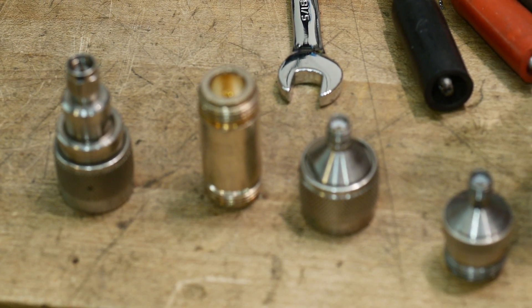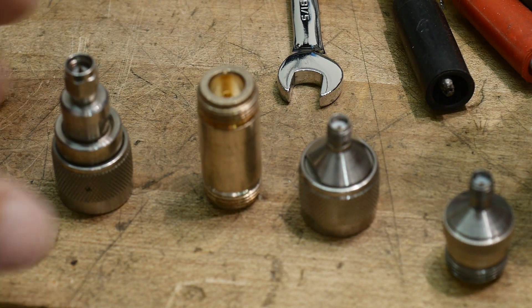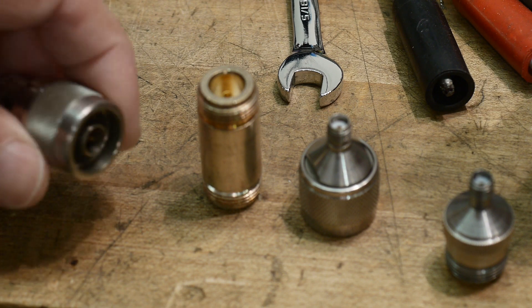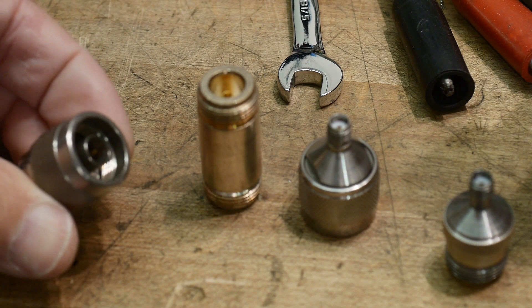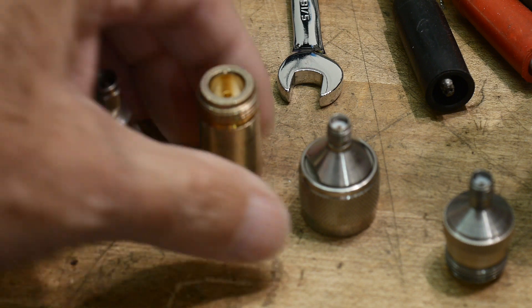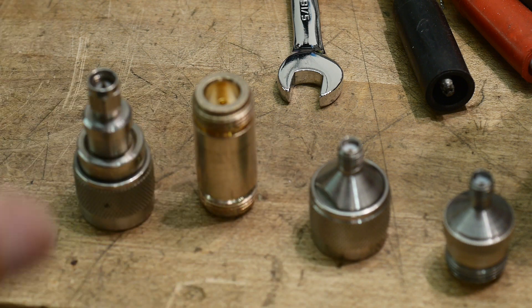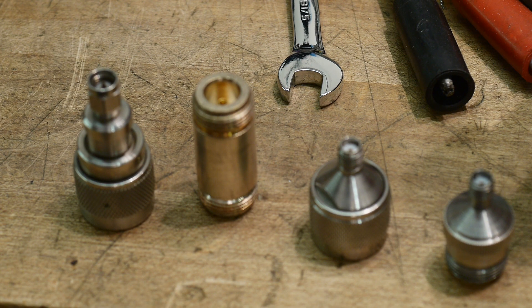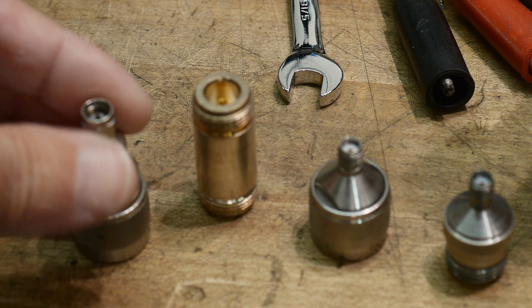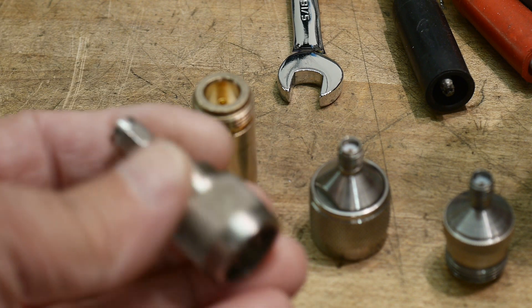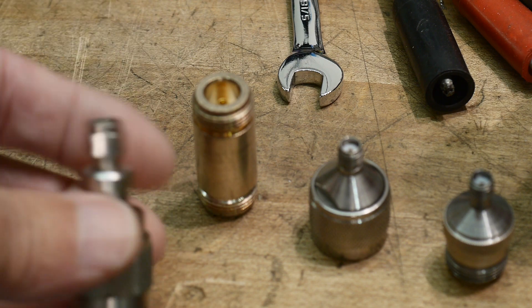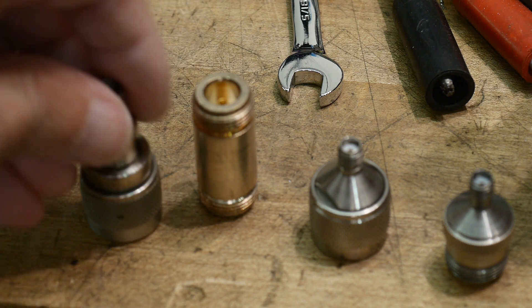I'm going to be using the best adapters that I have. N-type connectors are one of the lowest loss connectors and they're quite repeatable, so I'm going to use N connectors as much as I can. Now this thing is SMA, so I'm going to have to go at least to SMA. The only male SMA adapter I have is this one, and unfortunately it's also male on this end. So I really would like a female.